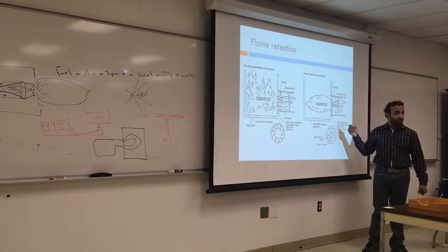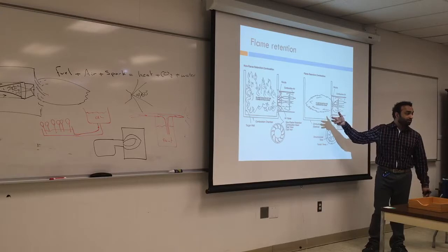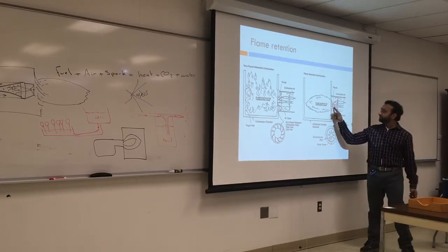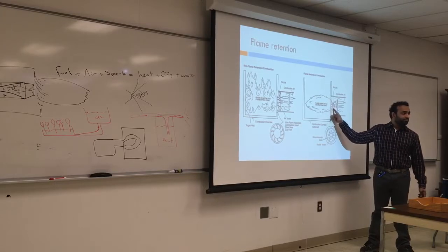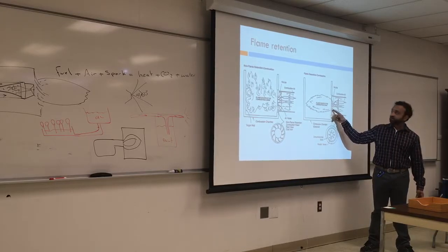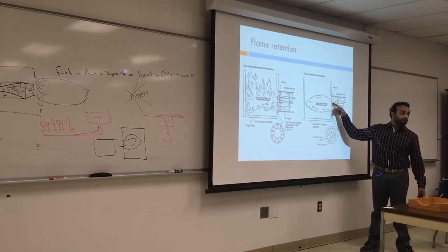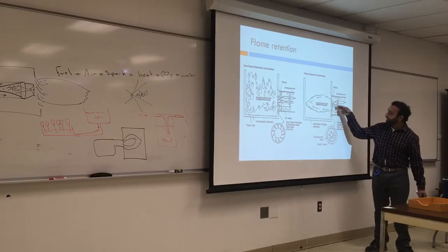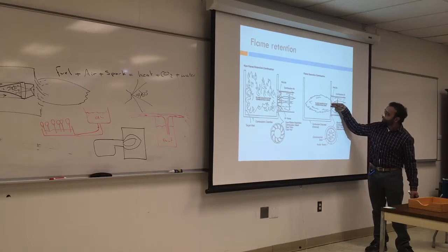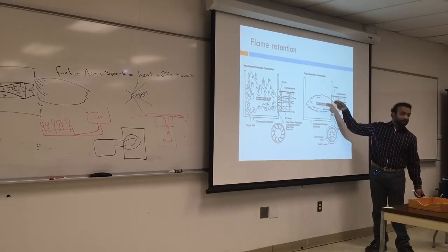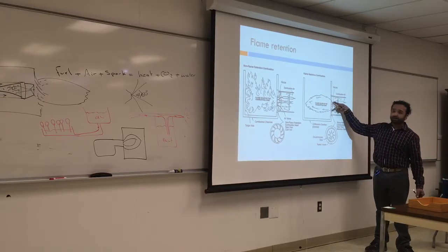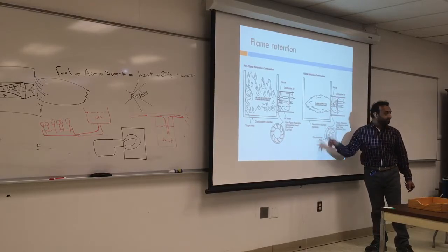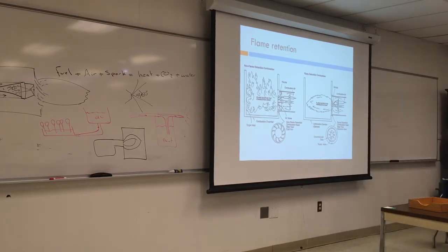But when you take it apart, put it back again, hopefully you put it correctly and you get the same shape of flame. If you see some drips in here, some drops of oil, you know something is not right, and the fuel might be hitting the turbulator plate before it goes out. So you can see how the angle is very important. It's supposed to fork in here and go out. If it's a little bit further, it's going to hit the plate, and you have some after drip inside the chamber, and that is not good at all.